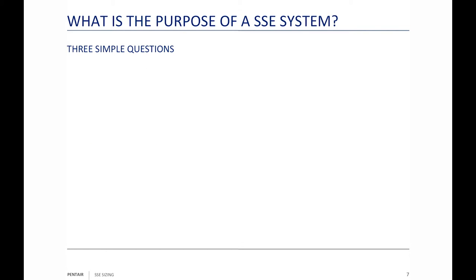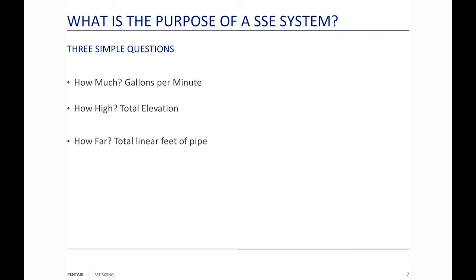There are three very simple questions you have to ask: How much, meaning gallons per minute? How high, meaning total elevation? And how far, meaning your total linear feet of pipe, from which you can calculate your friction loss. Those are the three questions. If you can answer those three questions, you're ready to go.